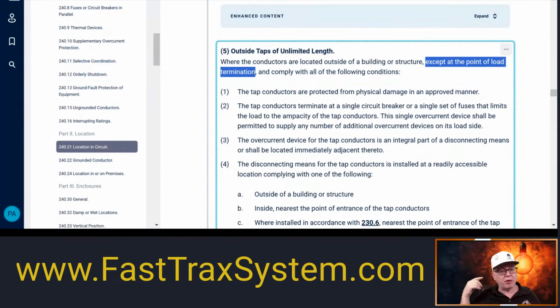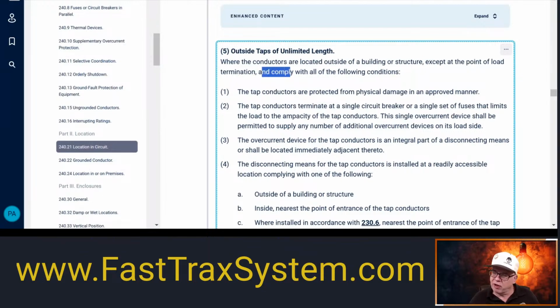Now it comes around the building, but it's obviously got to get into the building to get to a piece of equipment, whether it's the panel or whatnot. So the outside portion of these taps is covered, not the portion that immediately comes in and has to terminate. And we'll see rules on that when it tells us about the termination. It's going to be very similar to the rules we have, for example, for services, 230.70, outside or the nearest point of entry, once those tap conductors come in. And it tells us it has to comply with all the following conditions.